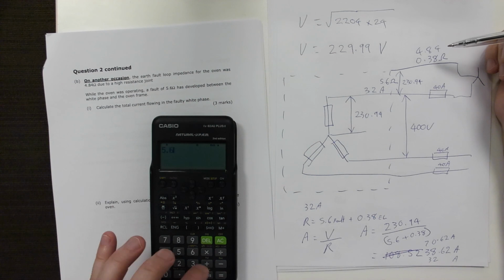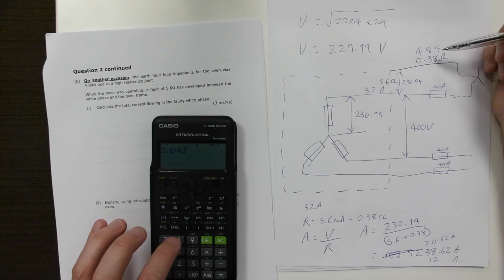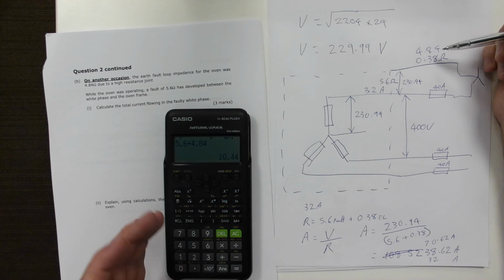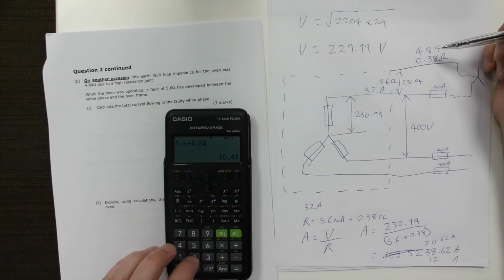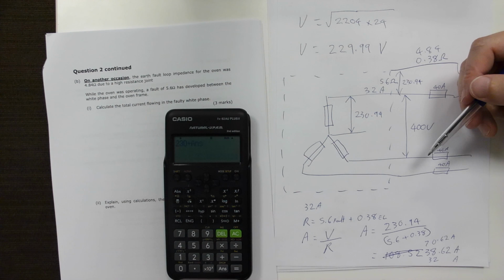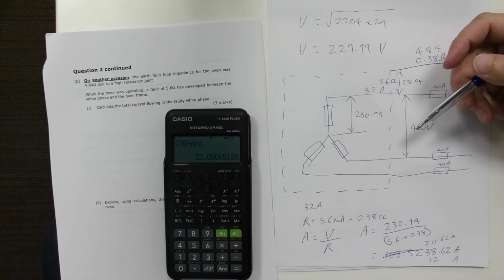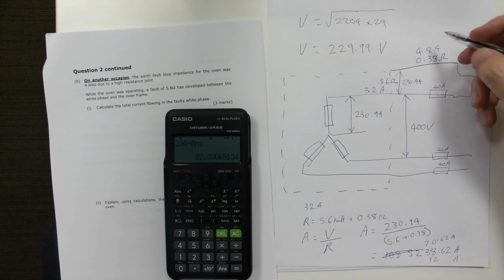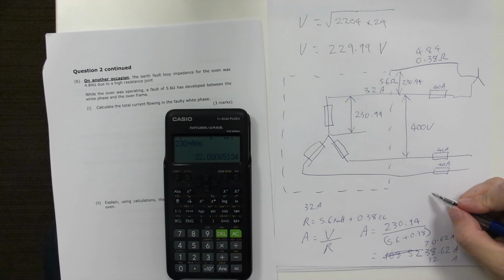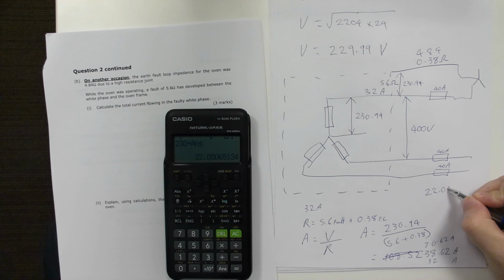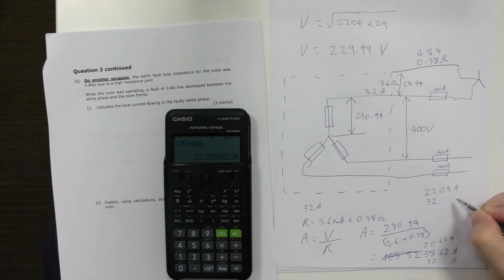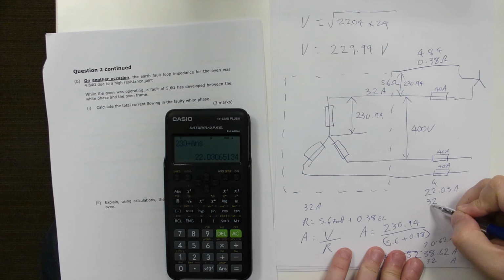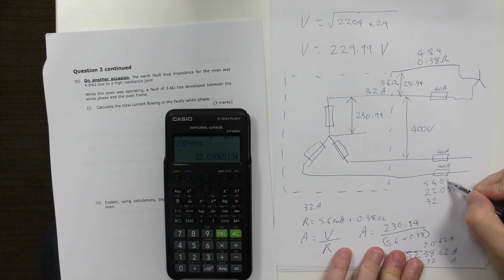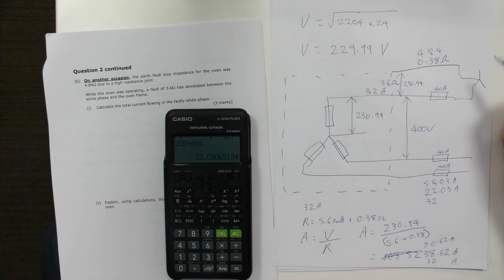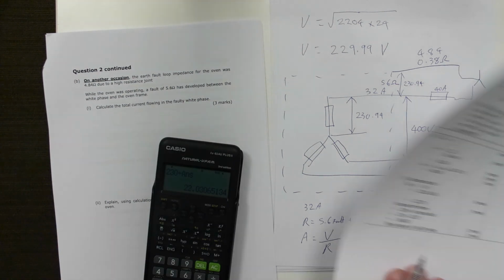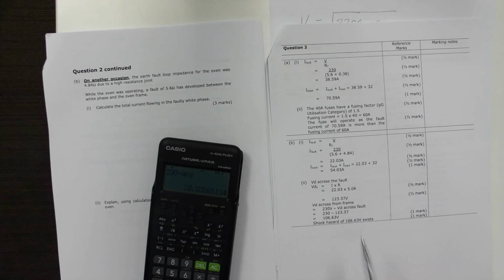So 5.6 plus 4.84 gives us 10.44. Since they're using 230, we'll use 230 volts. So 230 divided by answer, and we get 22.03. So we're now going to have a fault current of 22.03 amps plus our 32 amps from the oven. So we're going to end up with 54.03 amps total. We look at the answer sheet, they have the same thing, 54.03.